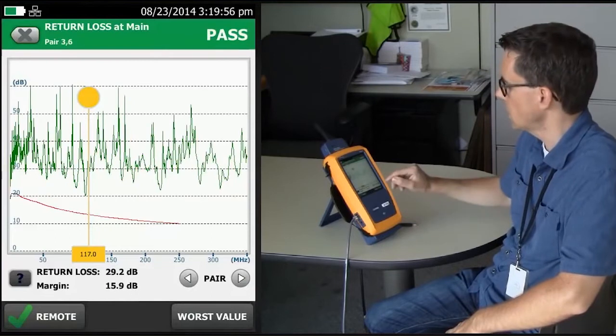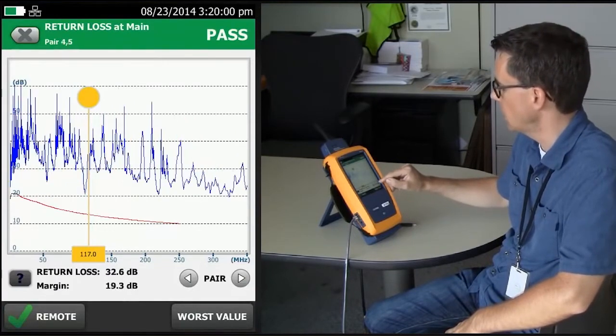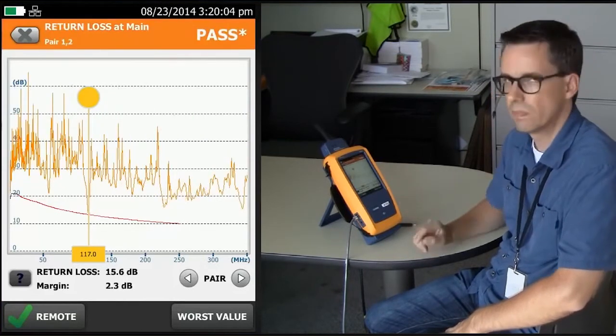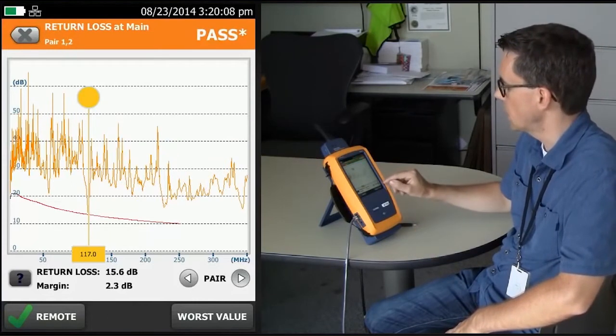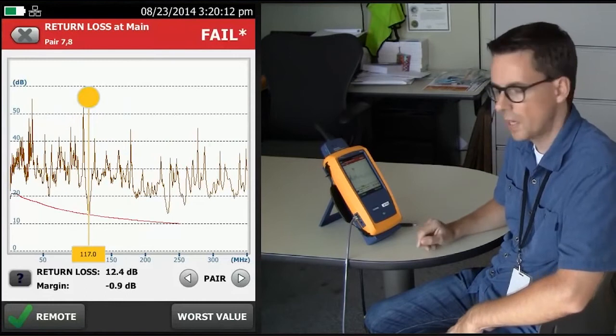If we go and look at our other pairs, like 3-6, we've got good margin. 4-5 is good margin, but also 1-2 barely passes. But like I said, we'll focus on just our 7-8 at the moment, the failing pair.